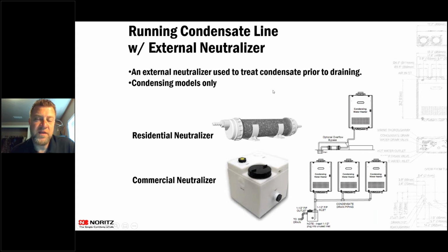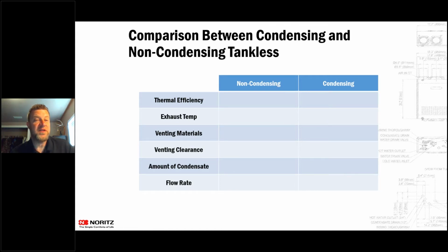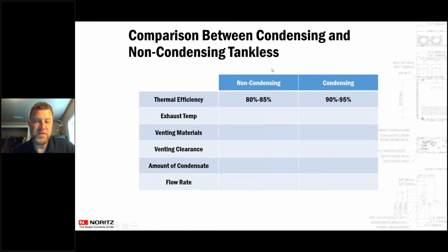So any other questions on the condensing and the condensate? Alrighty, so we will jump over to the comparisons between the condensing and the non-condensing when it comes to tankless. The first thing is going to be thermal efficiency, those UEF ratings. There are two different ways that they gauge it, either a UEF rating or a percentage rating. Non-condensing units could be between 80% to 85% efficient. Condensing units could be 90 to 95. With all the newer units that are coming out right now, those efficiencies are like 97, 98% efficient. They're getting very, very efficient with our pre-mix technology that we've brought out into the markets.